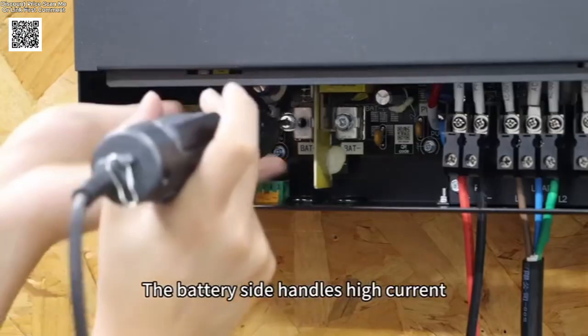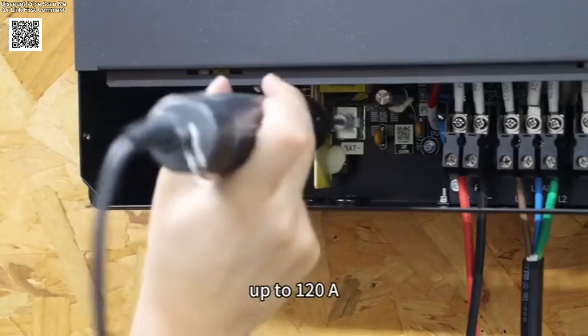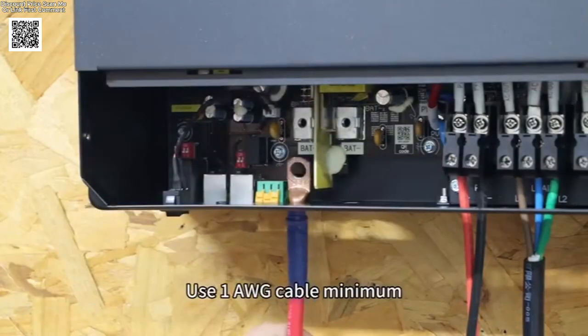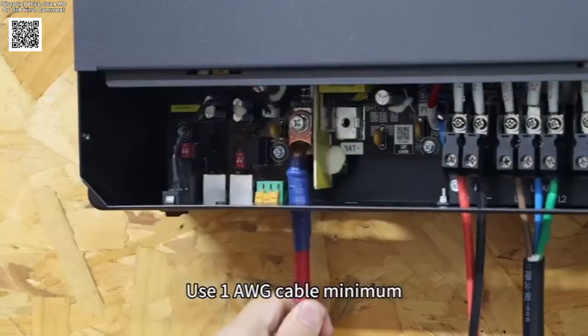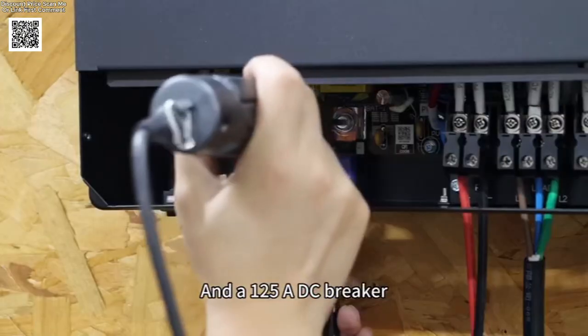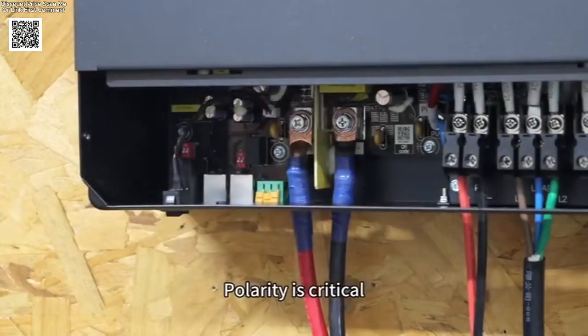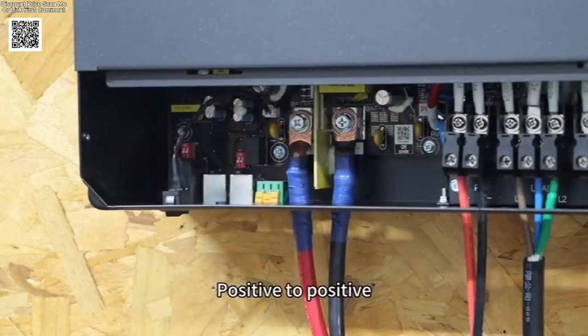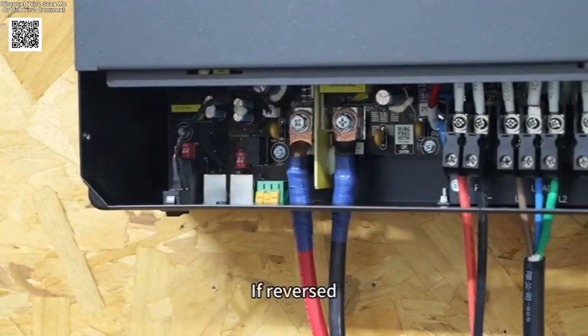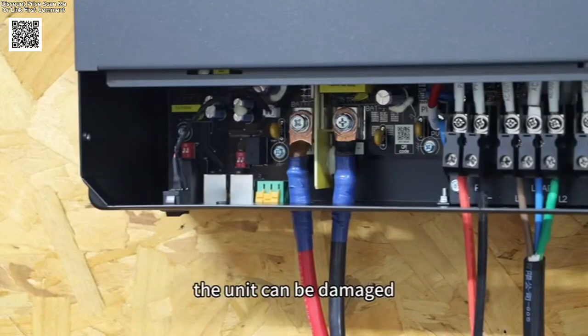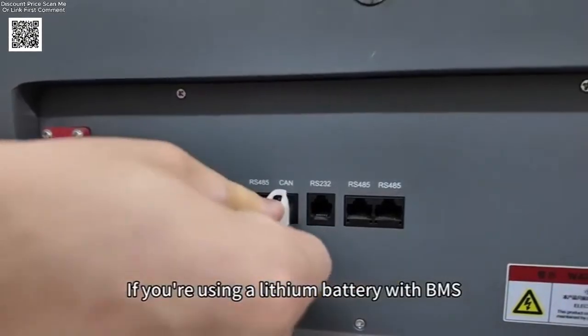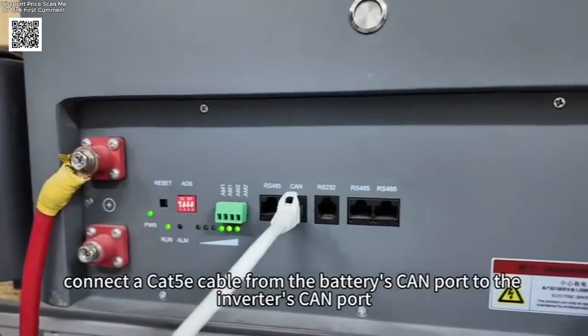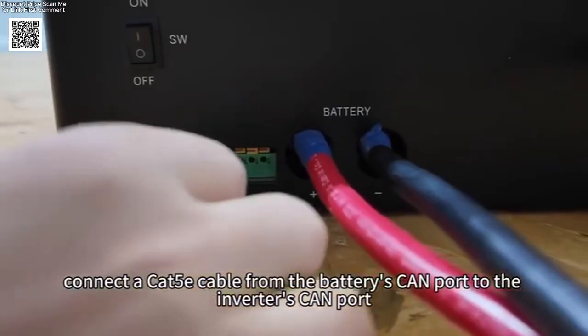The battery side handles high current, up to 120 amps. Use 1 AWG cable minimum and a 125 amp DC breaker. Polarity is critical, positive to positive, negative to negative. If reversed, the unit can be damaged. If you are using a lithium battery with BMS, connect the Cat 5e cable from the battery's CAN port to the inverter's CAN port.